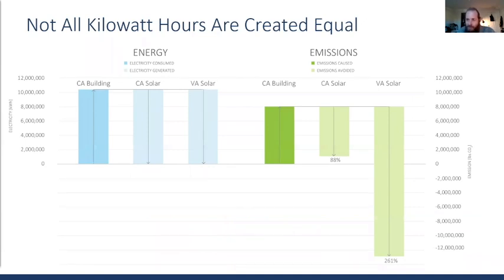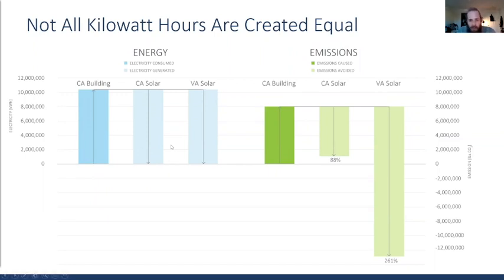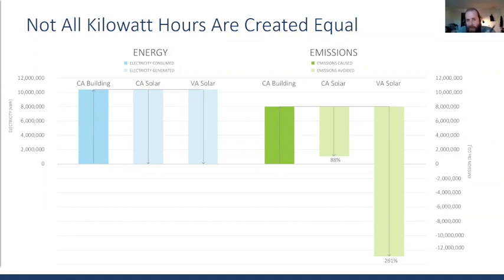I like to start with this slide as an introduction to timing and location. On the left, we have a building in California that consumes a certain amount of electricity and has also procured the same amount via solar — either in California or Virginia — so it's net zero energy on an annual basis. But the emissions implications are more complex. The same building in California causes emissions by adding load to the grid; conversely, adding that much solar only displaces about three-quarters of the emissions caused, because solar produces in the middle of the day and displaces a mix of natural gas and renewables. That's the key issue: when you consume or generate electricity really matters.